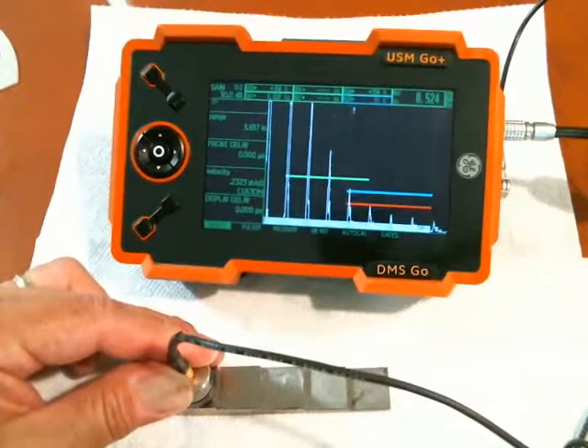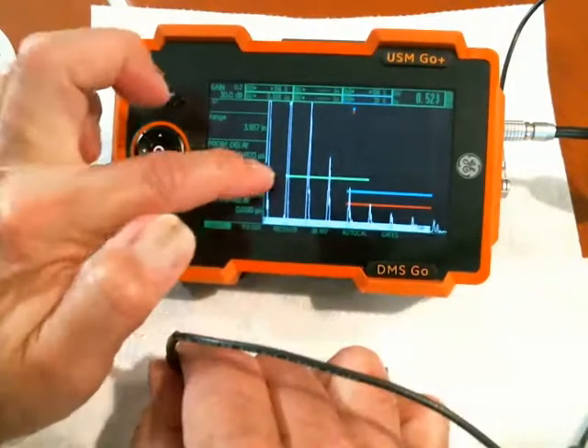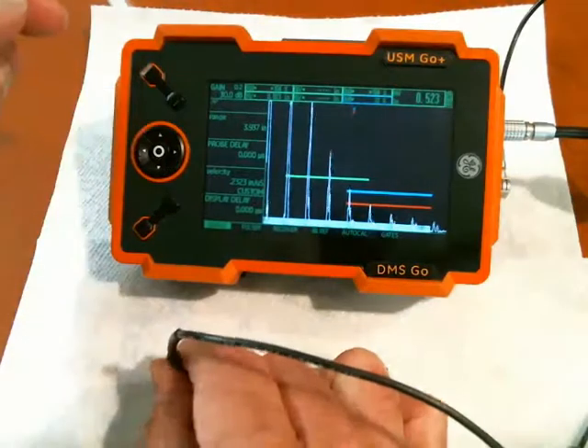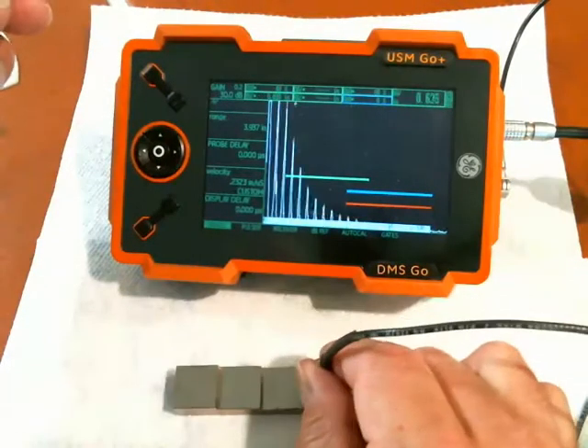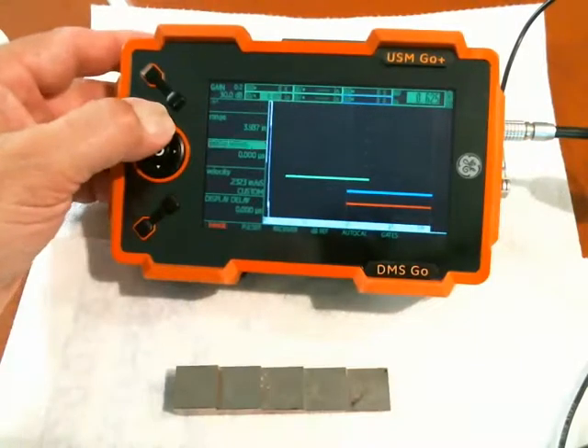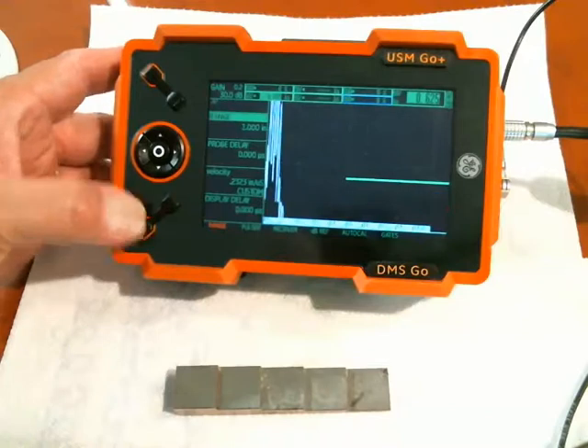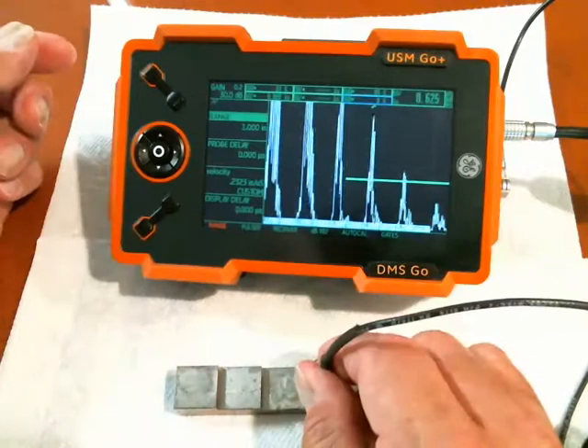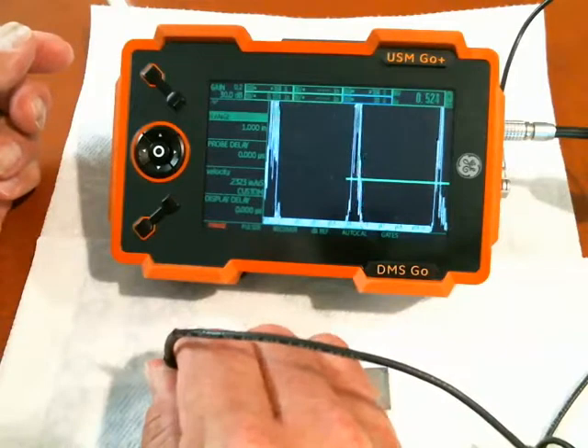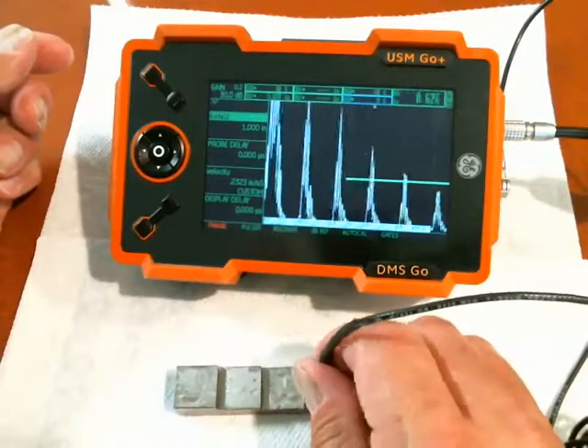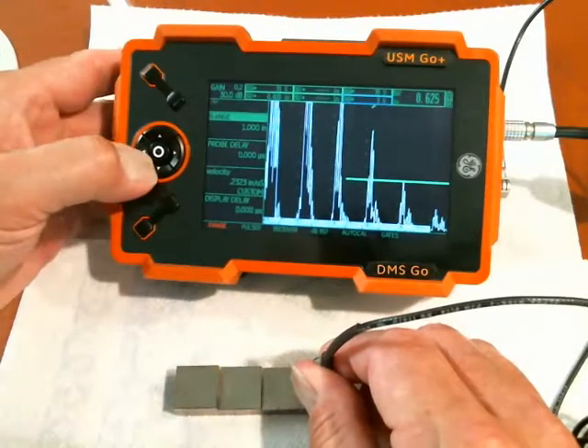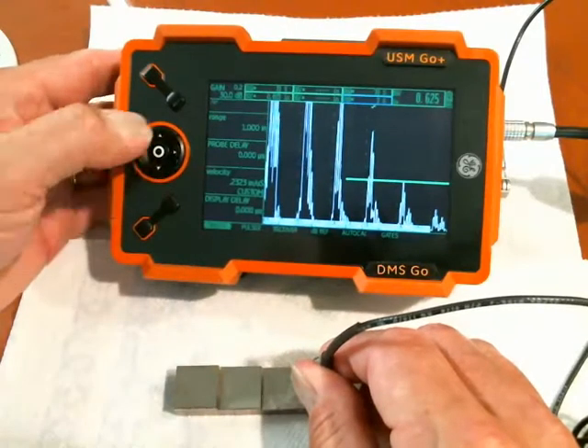One of the first things we're going to look at is gate A is positioned fairly far out. And our display range — if I want to look at a thinner block later on, a 0.2 inch block — our range is inconveniently long. So we're going to back down to one inch of range. There's my 0.2, there's my 0.5 inch. If I want to measure thinner materials, first thing I want to do is move my A gate in to make it possible to look at thinner materials.